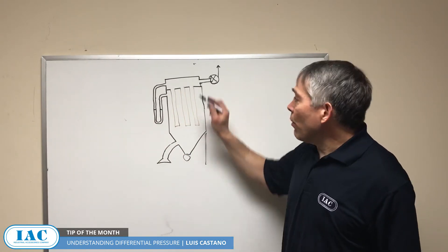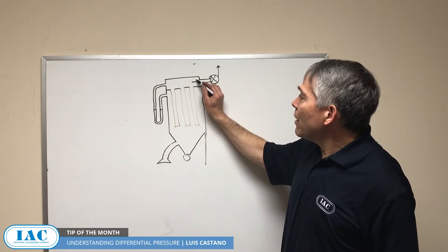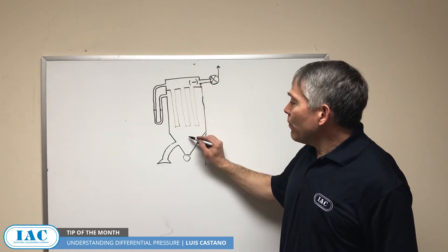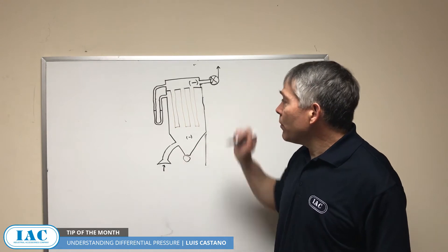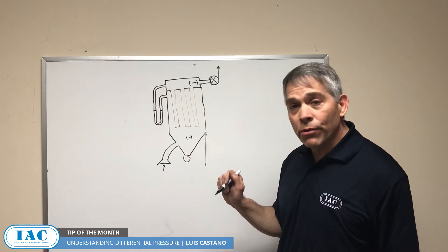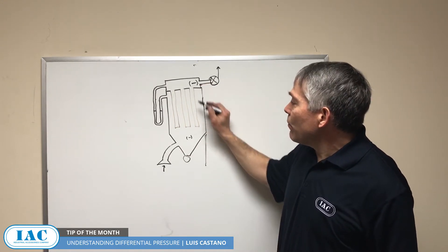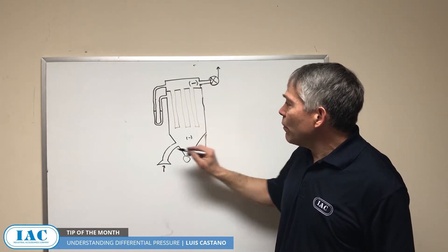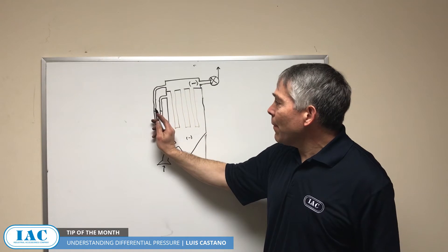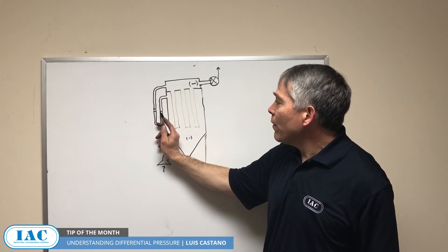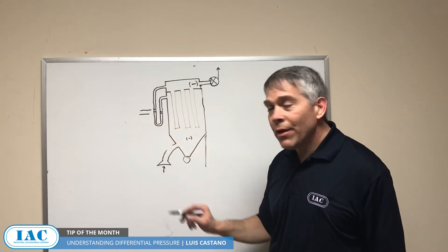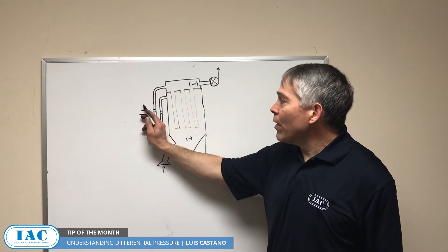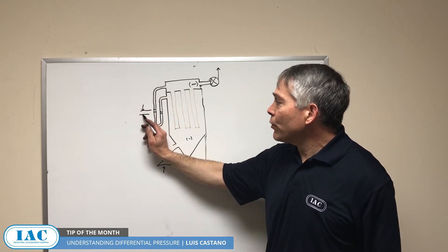When you turn the fan on, you get a negative here. That negative comes this way and that's how the bag house suctions and that's how it functions. You notice that this negative is larger than this one and that makes this water column go up versus this one. So now we have a difference here, and that is what differential pressure is.